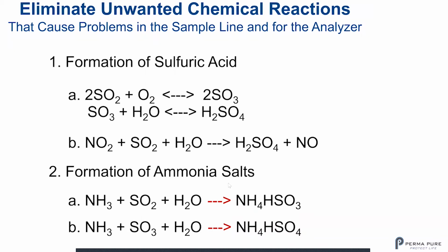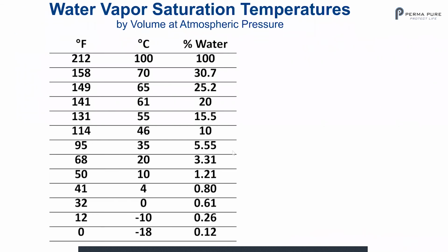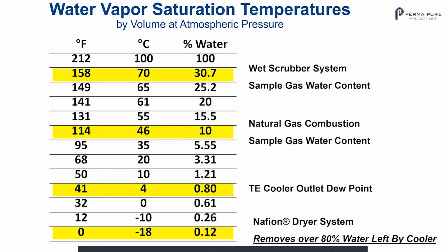Then you can also have the formation of ammonia salts if you have ammonia in your sample stream. Your ammonia plus SO2 and water gives you NH4HSO3, and you can also form NH4HSO4 when you have SO3. These ammonia salts have been known to plug many sample lines. So here's your water vapor saturation pressures I want to talk about a little bit. The first level is for a wet scrubber system coming off of a typical CEMS system. You're up to a dew point of 70 degrees C in your stack, which is about 30% water.